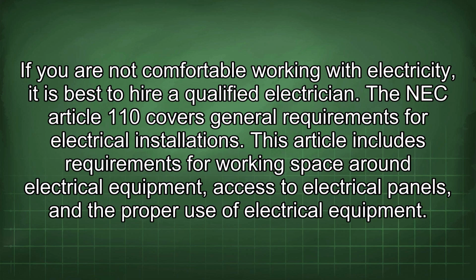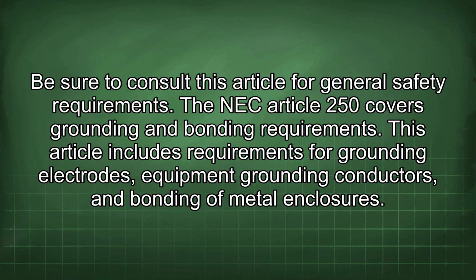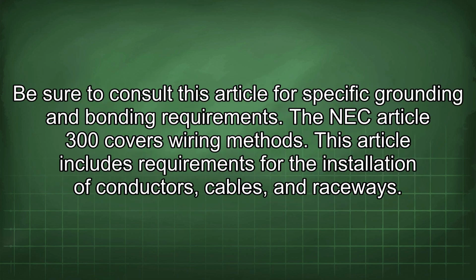The NEC Article 110 covers general requirements for electrical installations. This article includes requirements for working space around electrical equipment, access to electrical panels, and the proper use of electrical equipment. Be sure to consult this article for general safety requirements. The NEC Article 250 covers grounding and bonding requirements. This article includes requirements for grounding electrodes, equipment grounding conductors, and bonding of metal enclosures.